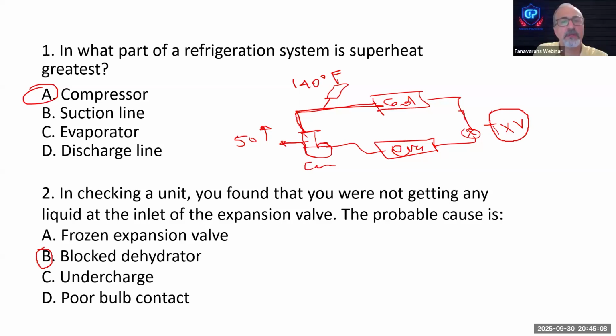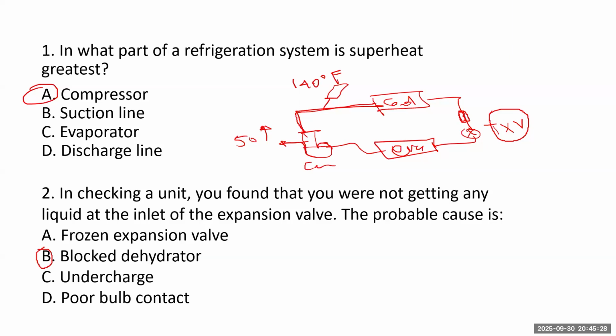Dehydrator is the filter dryer. There's a filter dryer in the liquid line. When the filter dryer is blocked, you're going to have too much pressure drop, and with too much pressure drop after the dryer, you're going to have some flash gas. So instead of 100% liquid going through the TX valve, you have some flash gas. That causes a problem for the system, and your TX valve doesn't work properly.